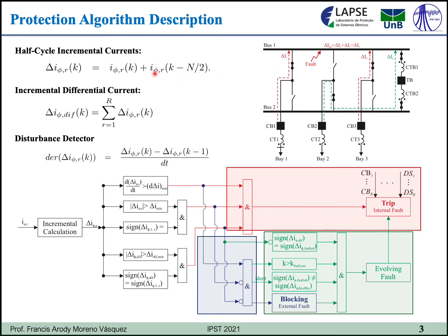So here we have our proposed method, and the method consists of the application of these concepts, differential and directional principles, but applied on the incremental currents. So the incremental currents are calculated with a half-cycle window, and there is a motivation for that, and it will be shown in the results section. And also we can calculate an incremental differential current, which is the sum of these incremental currents. And also we can have here a disturbance detector. We included a disturbance detector calculated as in this expression. And these signals are used for the formulation of the protection logic of the proposed method.